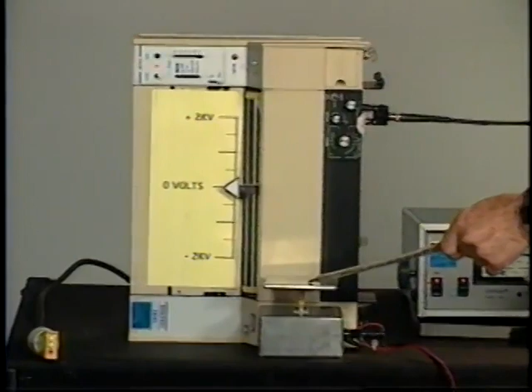We can show the calibration now by setting this power supply at 2 kilovolts, and we come over here and touch the electrometer head, and when I flip it on, it goes to minus 2 kilovolts. If I turn the switch to plus, it goes to plus 2 kilovolts, and if I remove the wand, that voltage stays there. That is the electrostatic voltage, and you notice that I can touch ground on the case here and put my finger on the plate and ground that voltage without any sensation of charge.